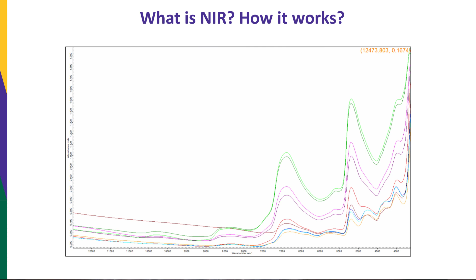This is the NIR we are using. It's a Bruker MPA equipment. We put the sample, and we put light, near-infrared light, on this sample. Some of that light is going to be absorbed. The rest of the light is going to be reflected or transmitted, depending on the sample, and we are going to measure with this equipment the diffuse reflected and the transmitted light. The NIR is going to give us this. This is a spectra. Each line is a sample, and that's all the NIR is going to give us if we don't calibrate it. Why?